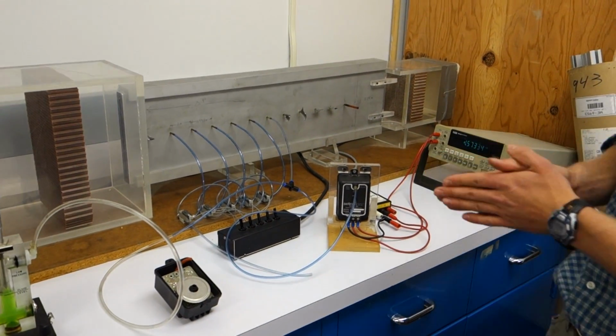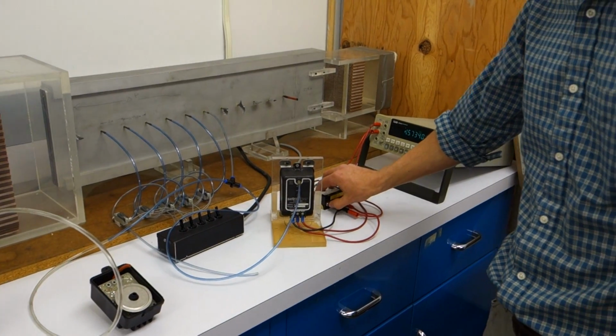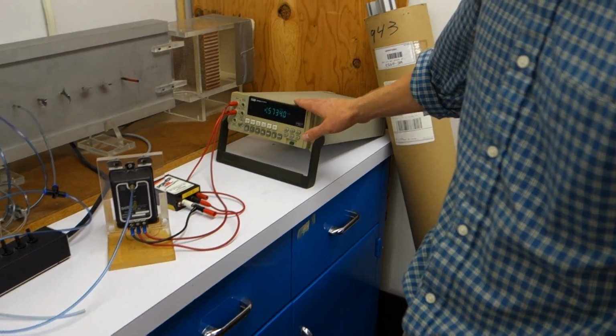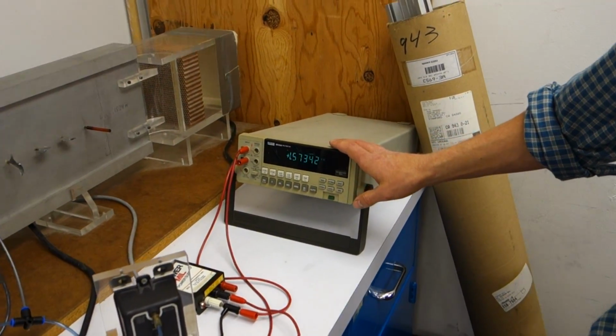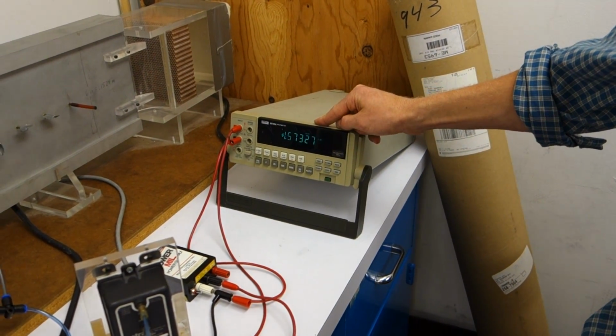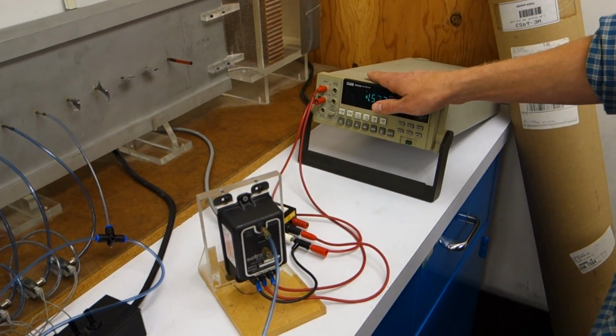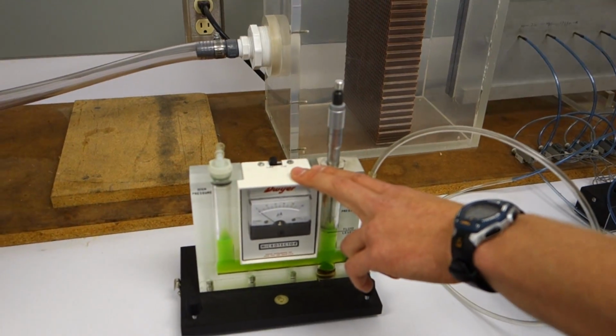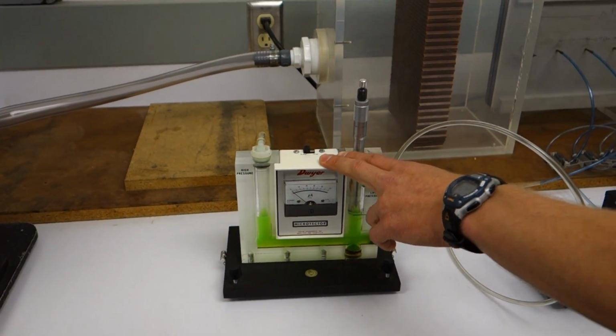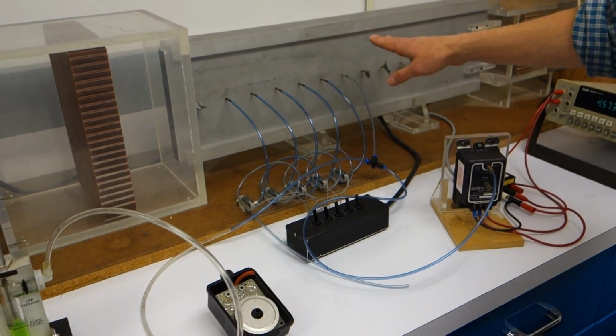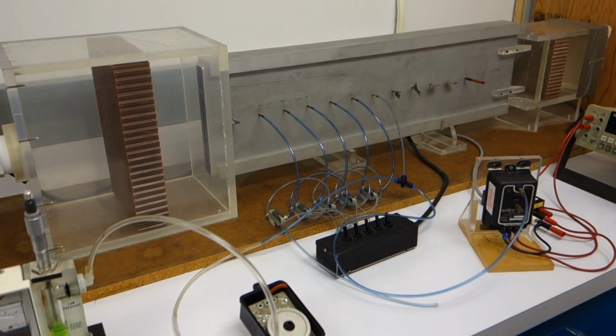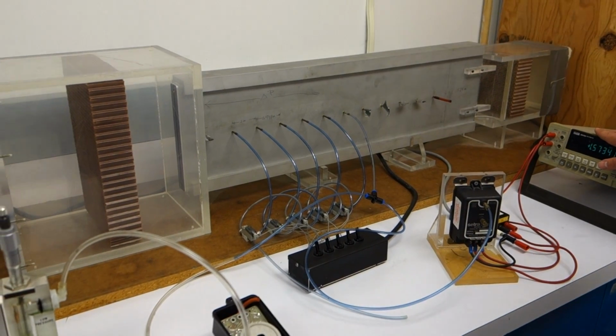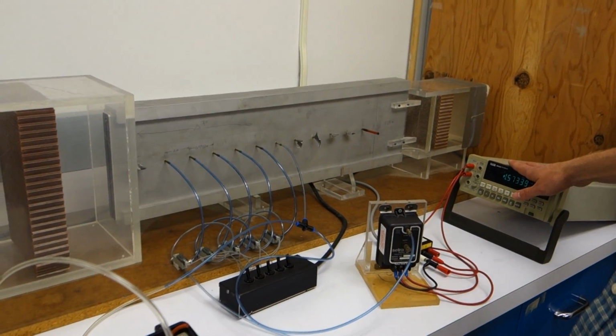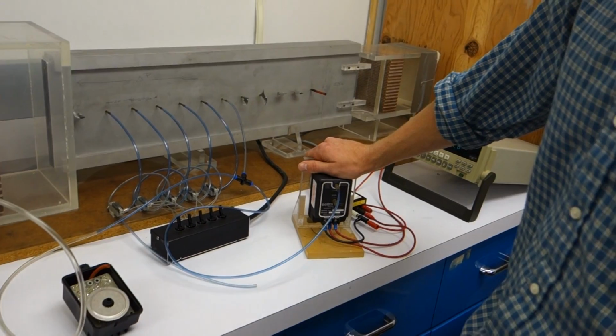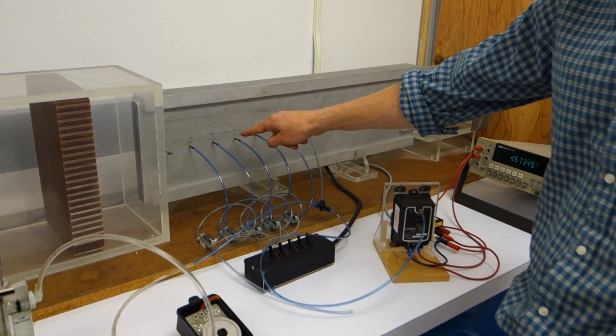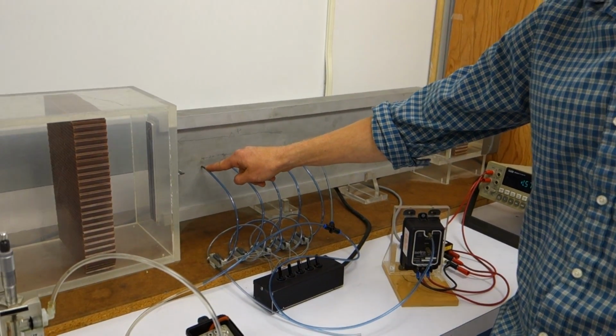But this is capacitive. So we'll make sure that the power supply is turned on and the voltmeter is turned on. This is reading volts, so we want to get a correlation between volts and pressure. We'll use the black box to give us volts, and we'll use the microtector to give us pressure, and we'll take measurements at a bunch of different flow rates in the duct, and we'll get a calibration curve for what a delta V, what a voltage, corresponds to in terms of pressure. Once we have that calibration curve, we can use our capacitive pressure transducer to measure the pressure drop as we work our way along the duct.